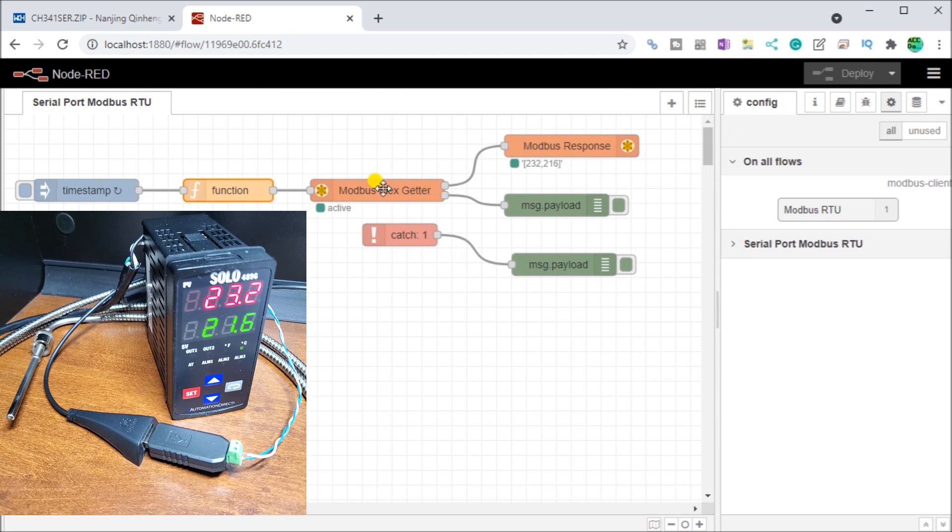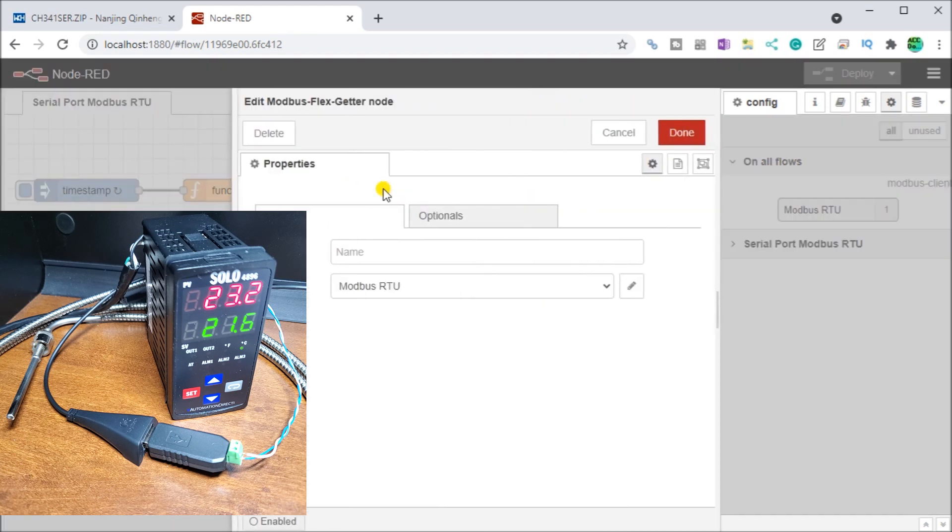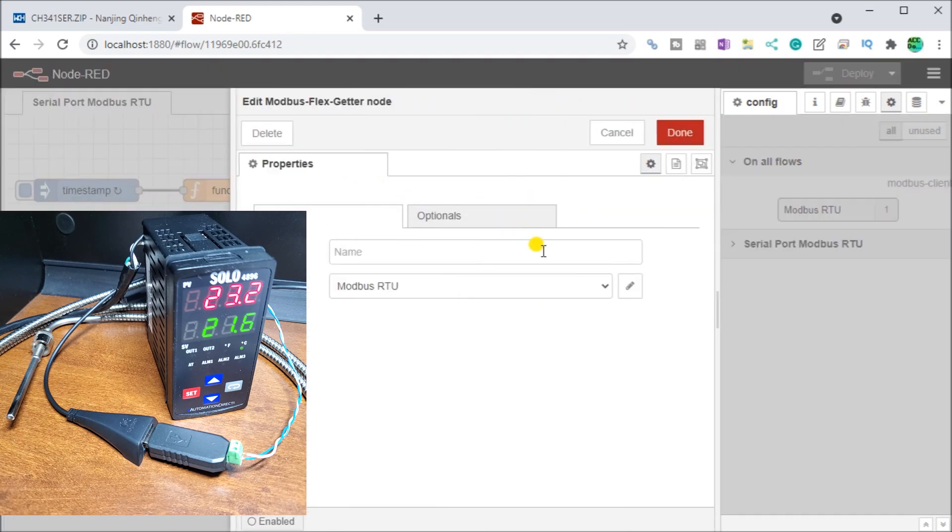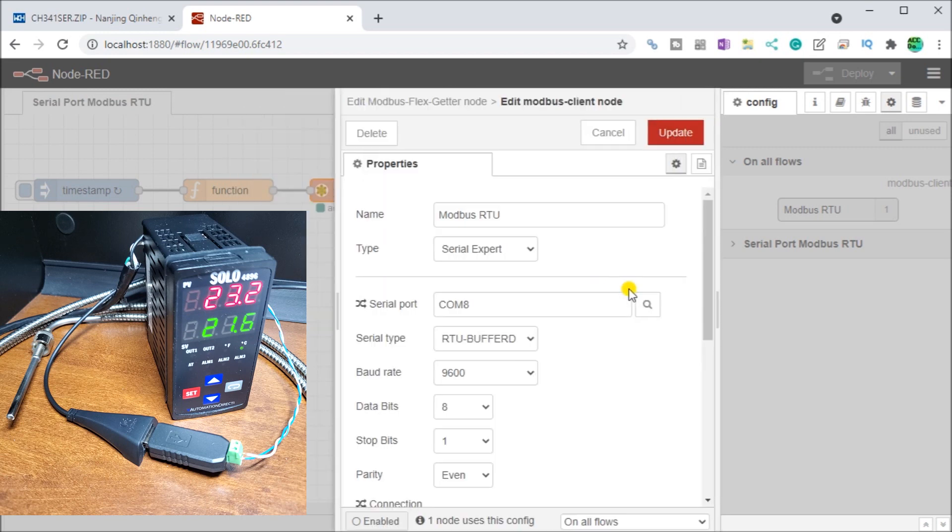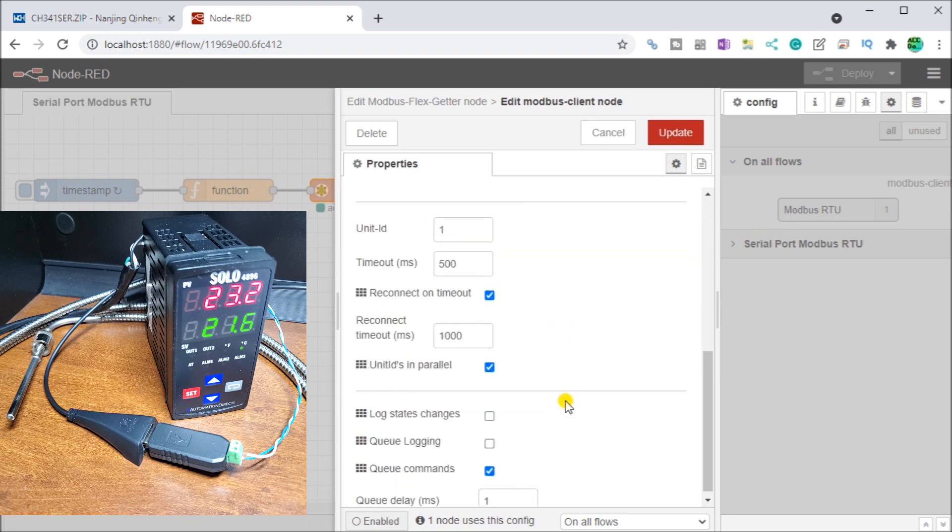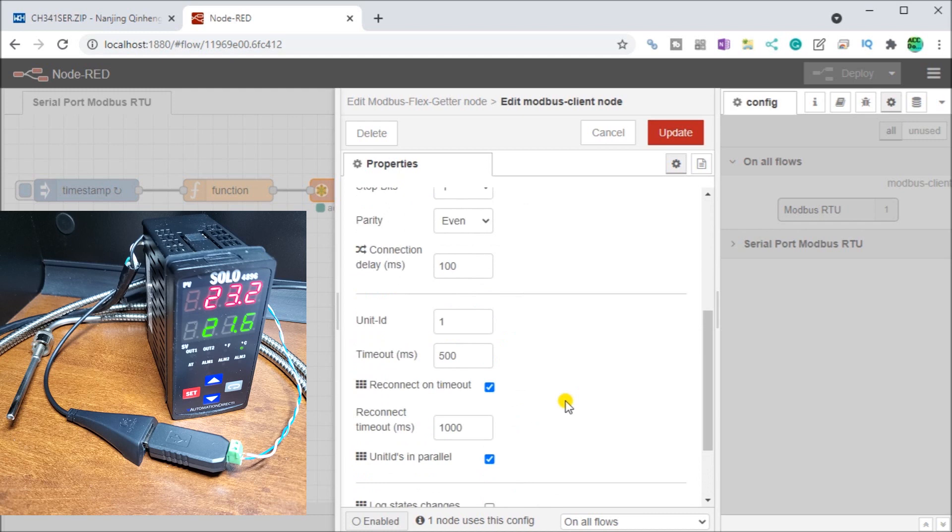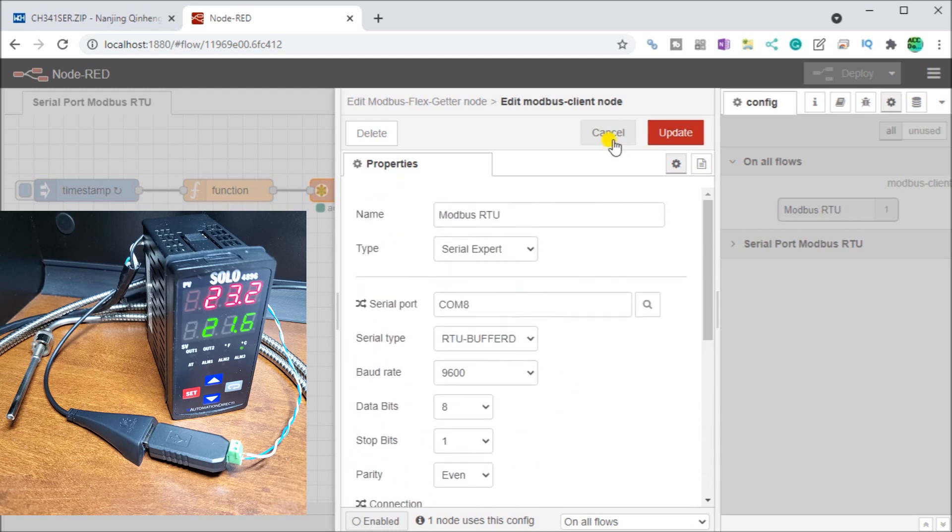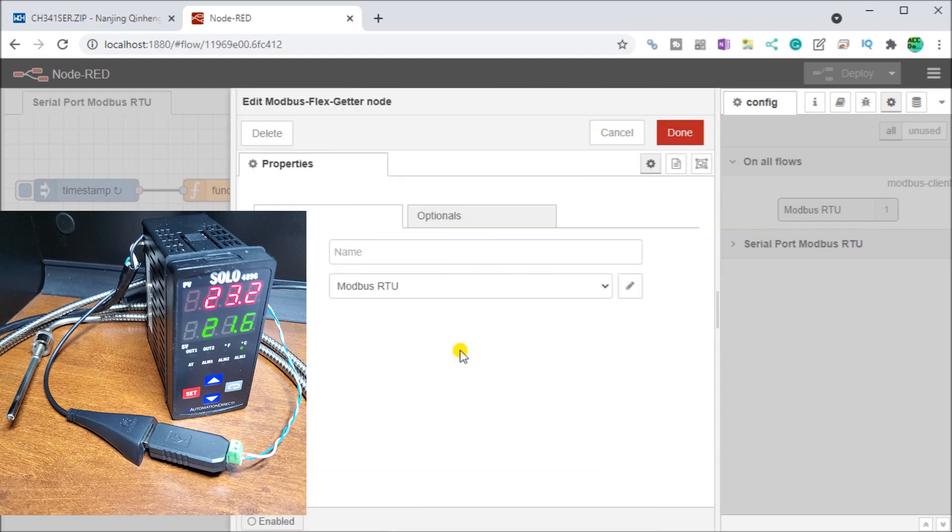And then what we do is we just go ahead and get that using the Modbus flex getter and our server. If we look at it, it's actually set up for COM number eight, which is our serial device. And then our serial is baud rate 9600, eight data bits, one stop bit, even parity. And then our connection timeouts.